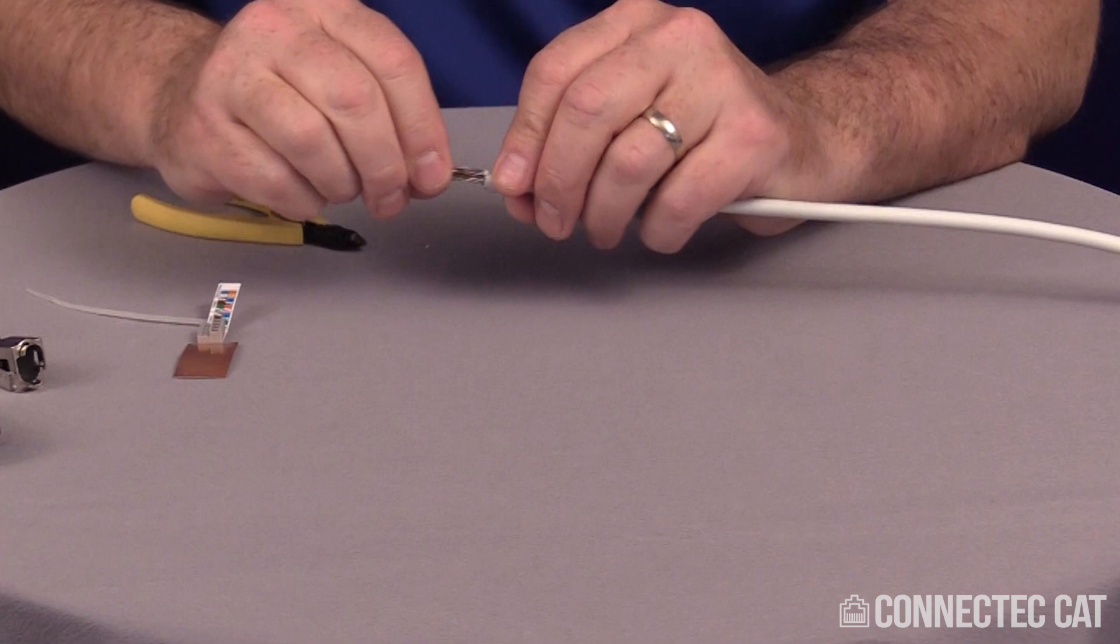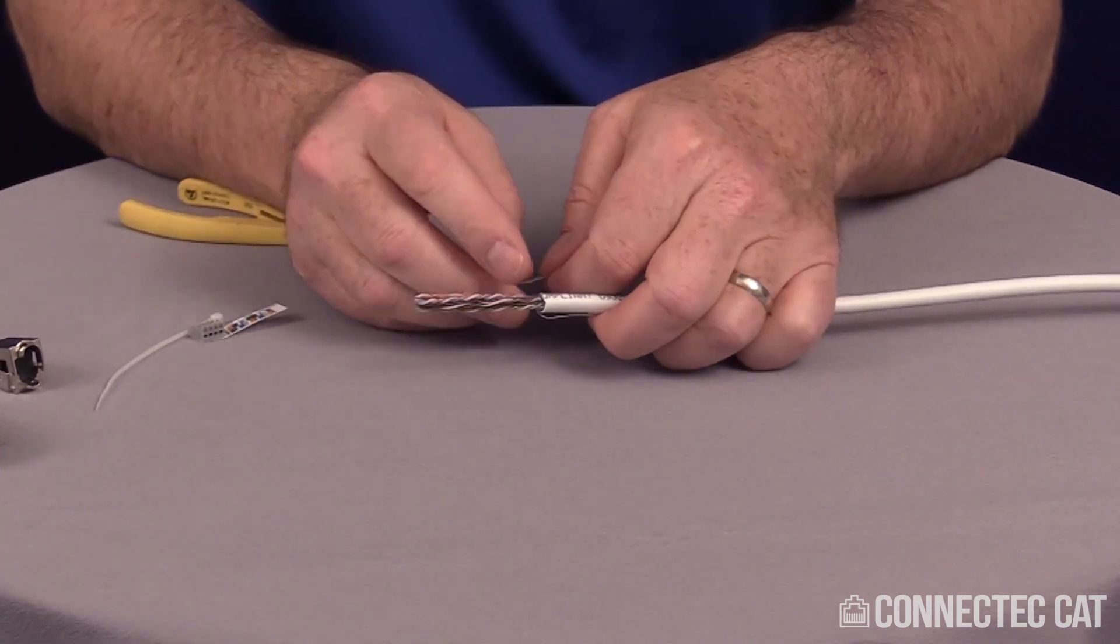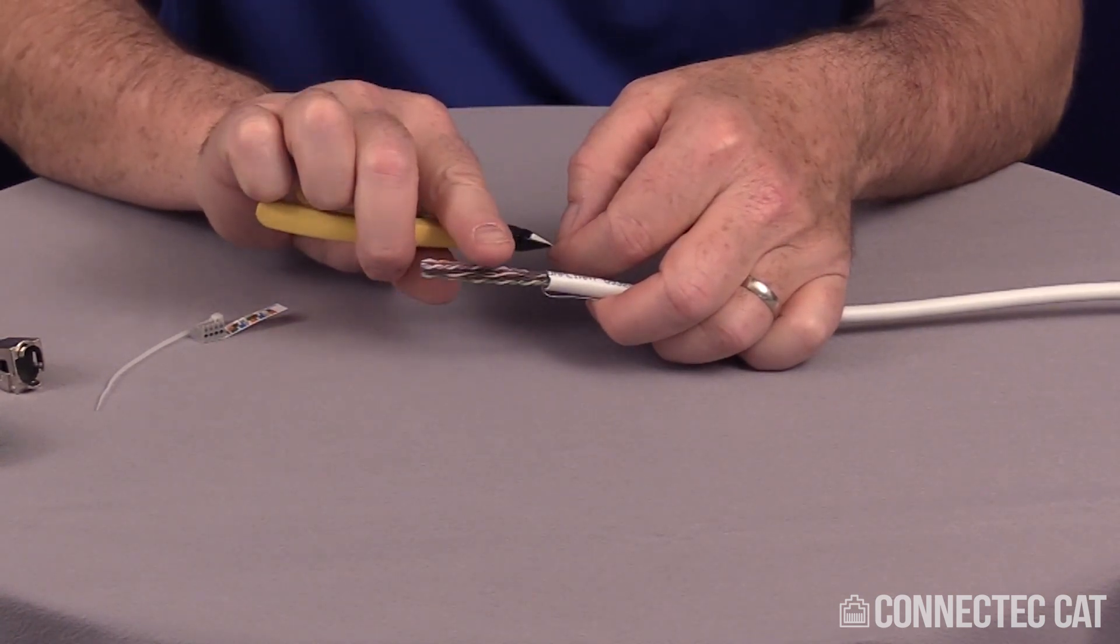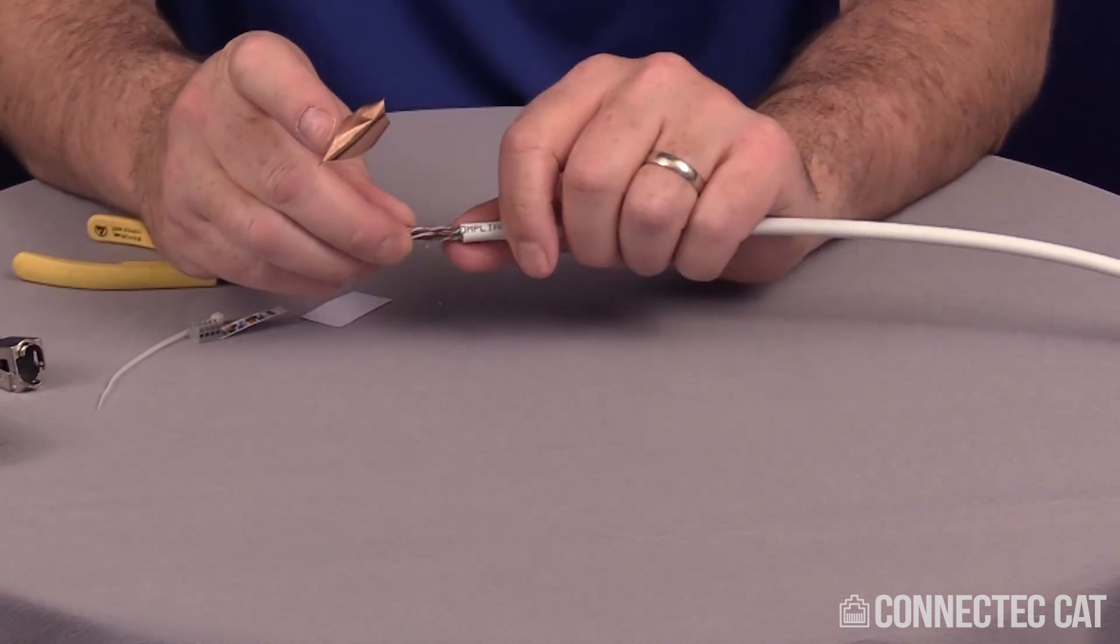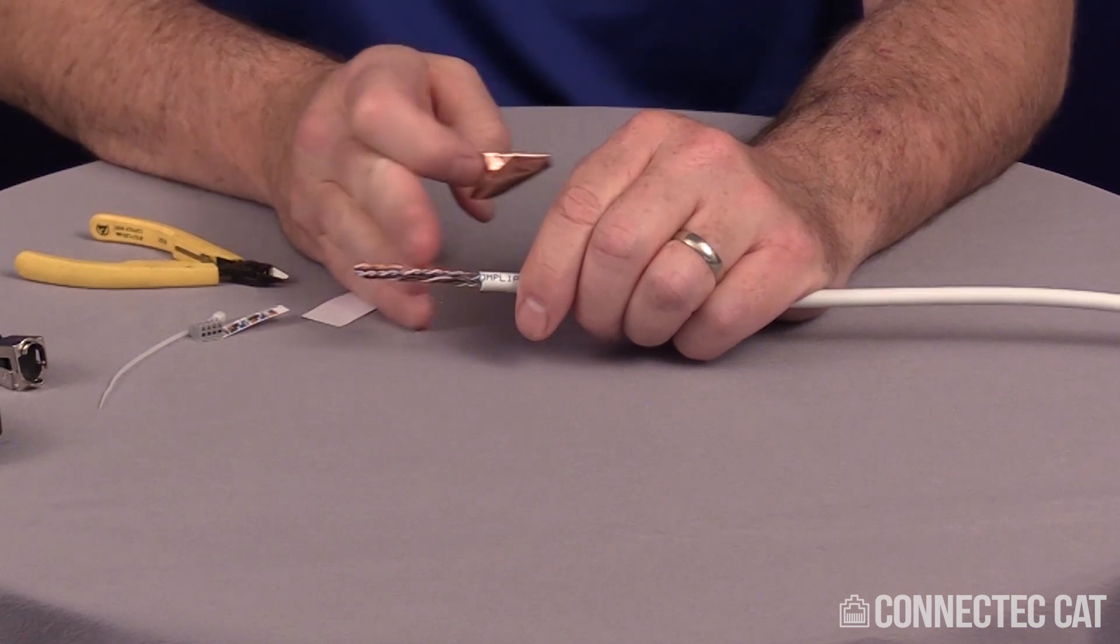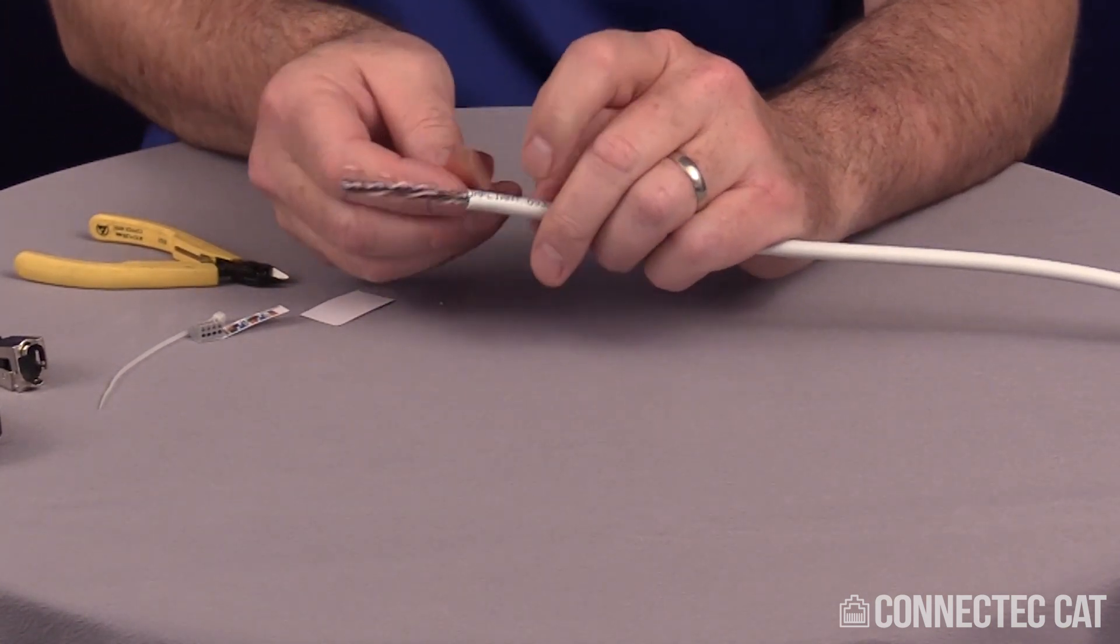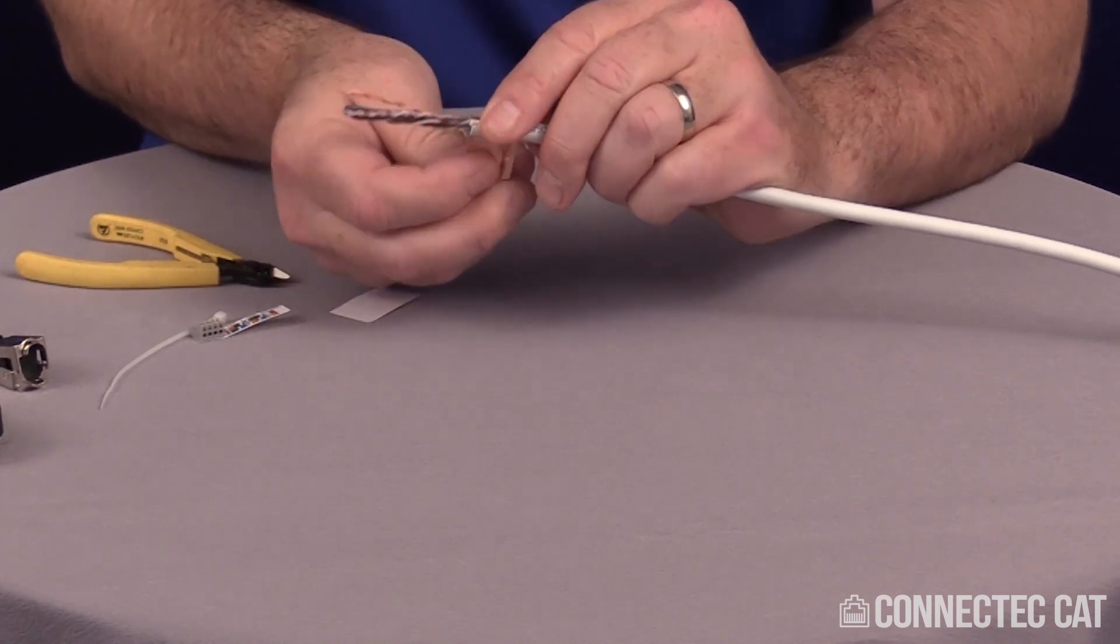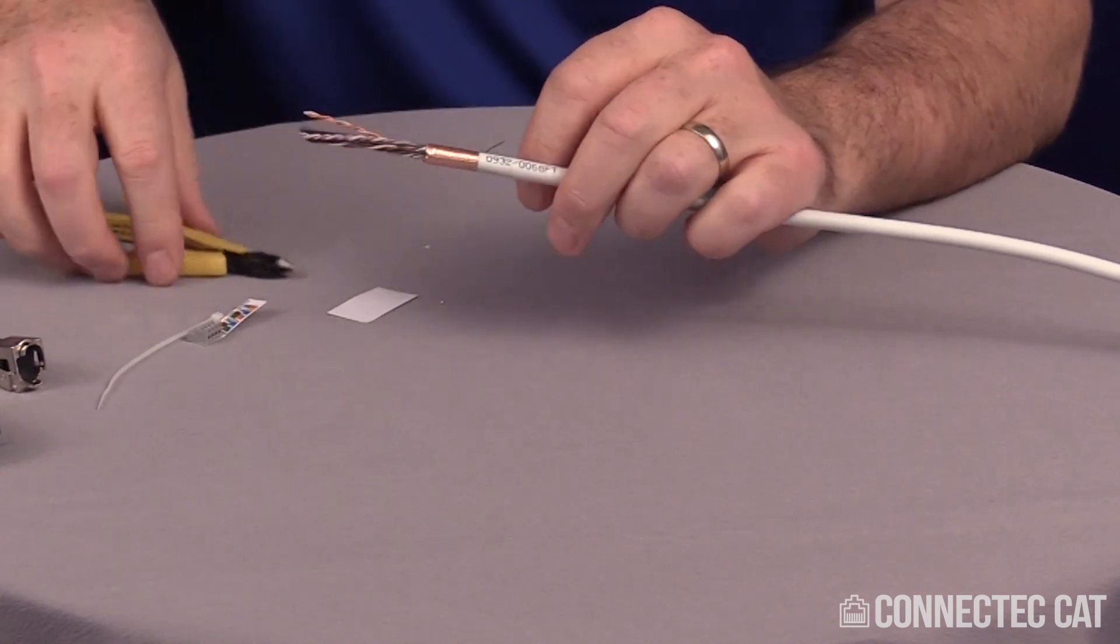Now I'm going to anchor my drain wire with the copper tape. Taking the copper tape, start at a corner. Then take your diagonal cutters, gently grip the copper, give it a little tug and it'll come right off. When you put the copper tape on, don't go past the jacket. If you go past the jacket, when these conductors bend back you could cut them and cause a short. Just below the jacket, lay the copper tape, make it nice and smooth, and wrap it around. Now I can cut off my excess drain wire.